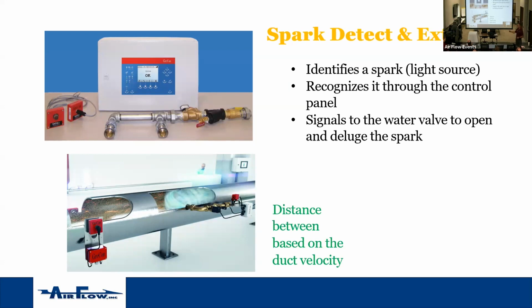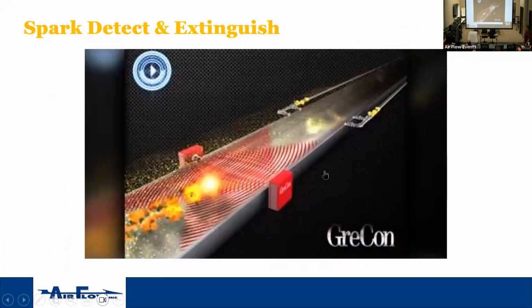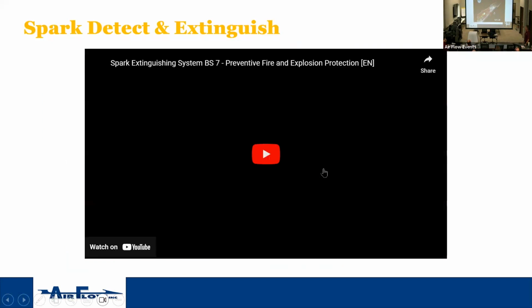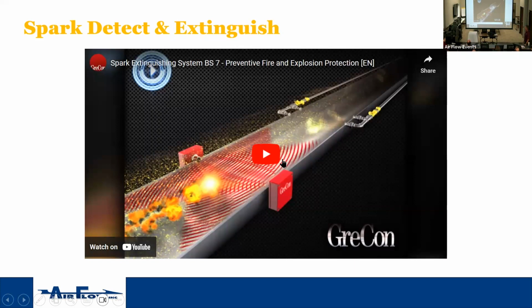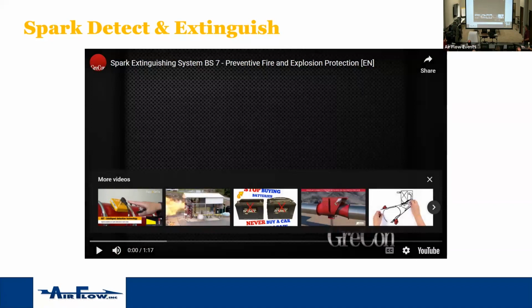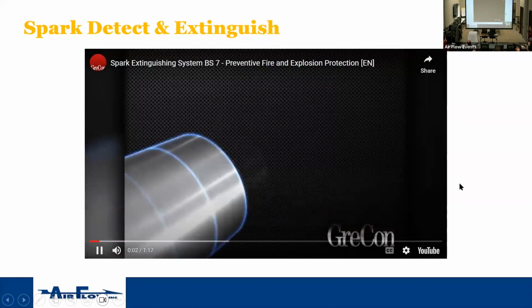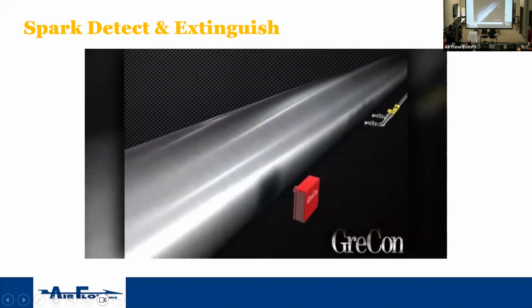You can monitor this. Any sparks can be monitored and pulled back to any BACnet DDC system through that control panel. You can go up to it and see how many times it's happened, how many devices, how many instances this is one off to stop the spark. Here's a little video on kind of how it works here. So this is GreCon's kind of the pictorial.